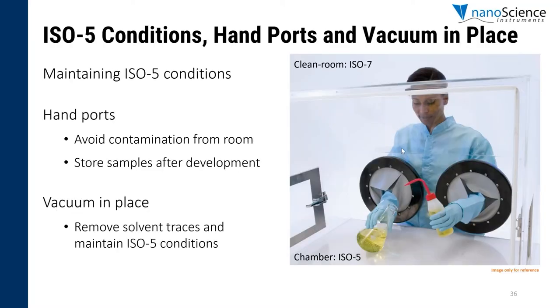Let's say you're operating our unit inside a clean room under ISO 7 conditions, but you want to do sample development at ISO 5 conditions. If you open the door of the electrospinning machine, the unit with ISO 5 conditions will be contaminated by the ISO 7 environment, so this might not be ideal for your application needs. Our solution is to offer hand ports to avoid cross-contamination between different environments. This allows you to maintain climate conditioning inside the chamber and even package or store the sample at ISO 5 conditions.